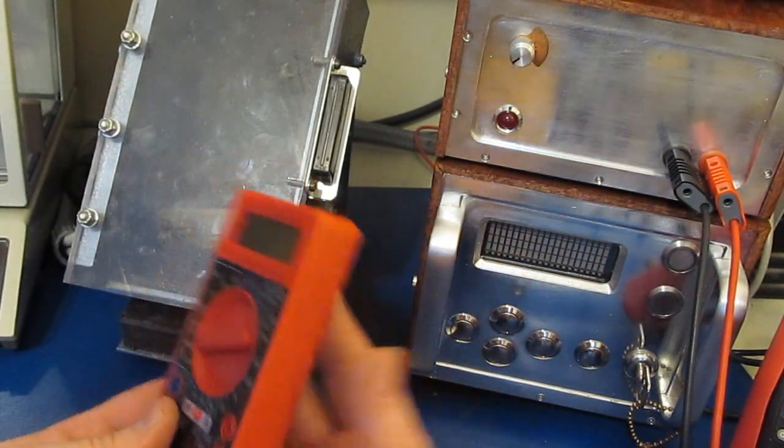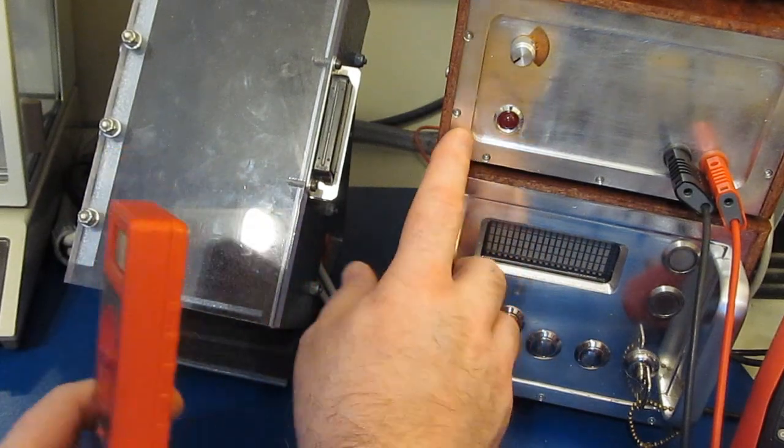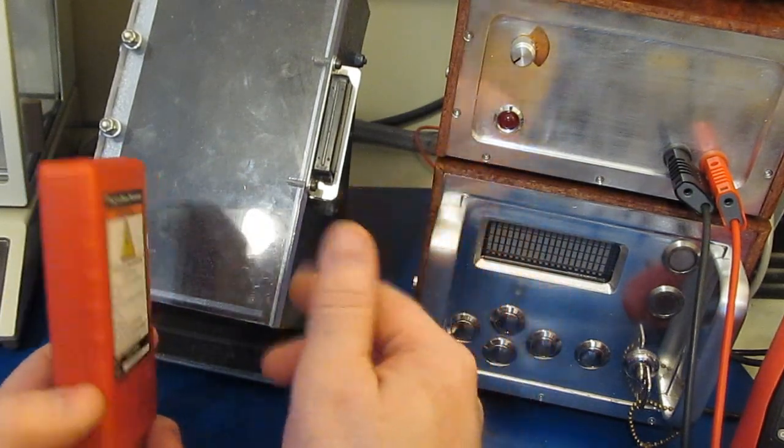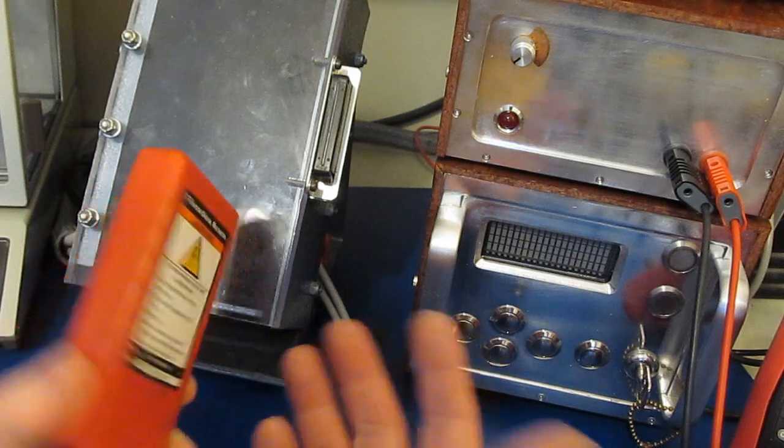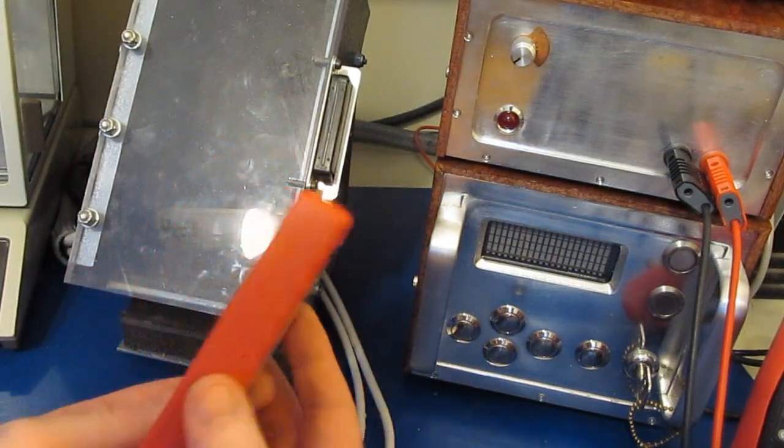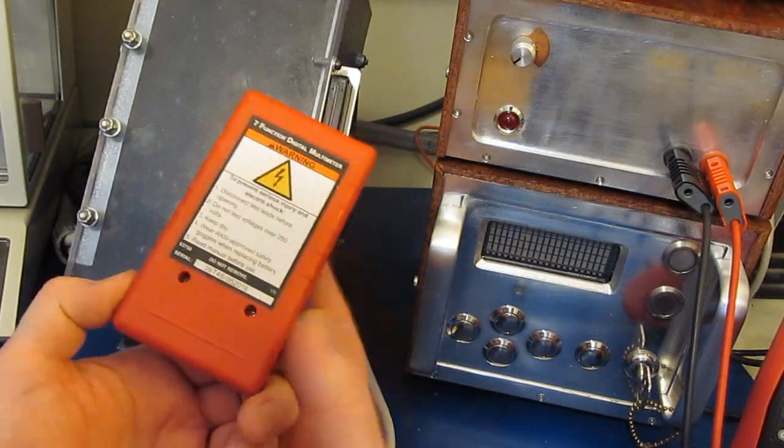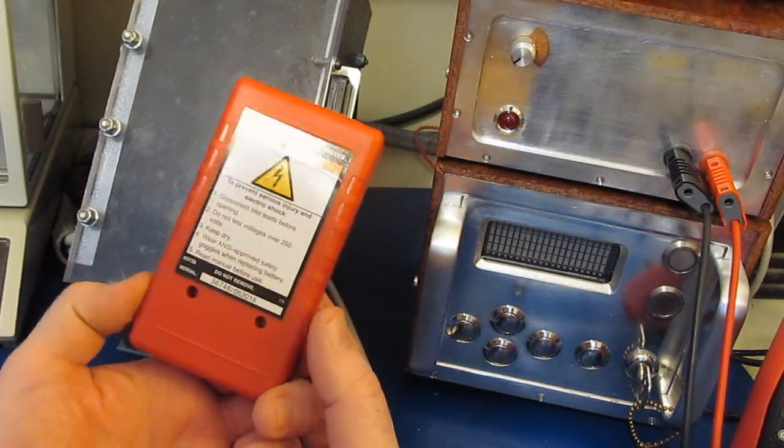Basically what I was trying to do with this generator is mimic the energy available in a half of a cycle on an AC main. It's not a lot of energy, but it will typically do enough damage to these meters where we can get an idea how they may behave with a higher energy transient, like the IEC surge test.